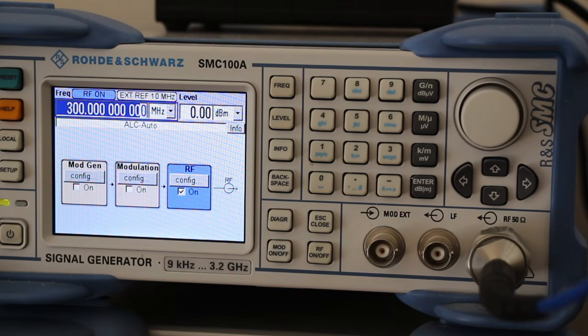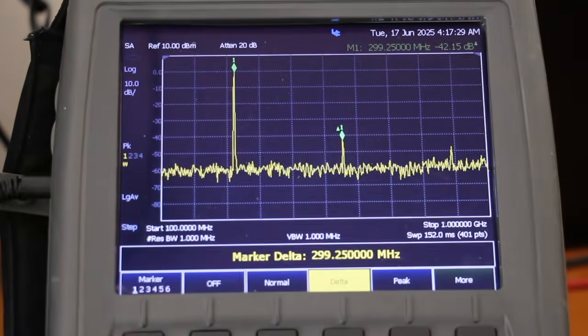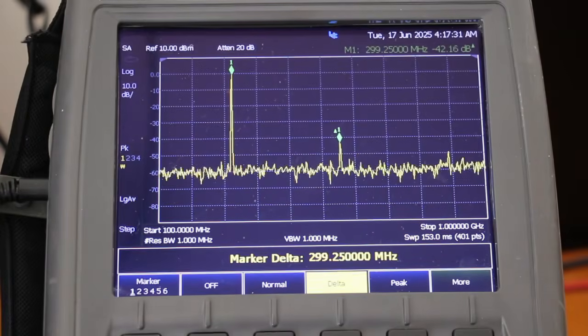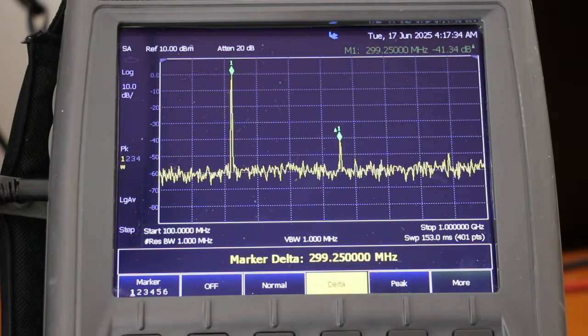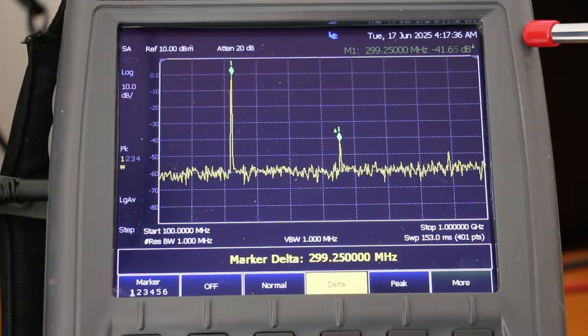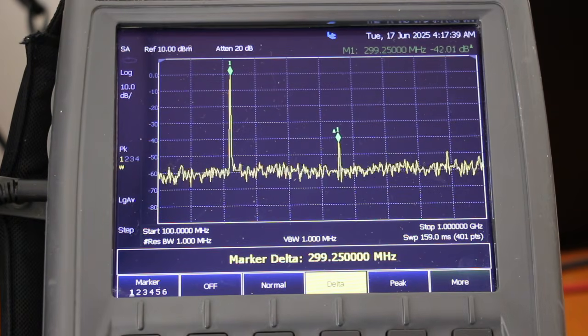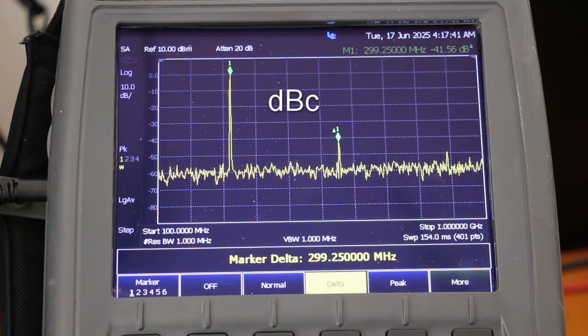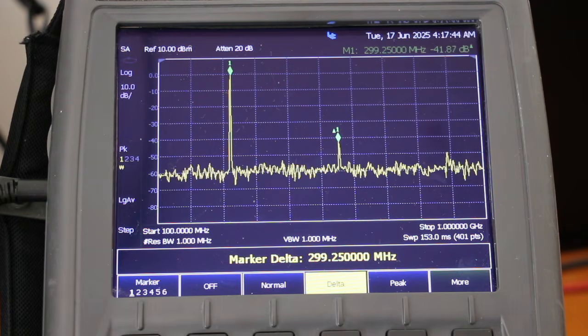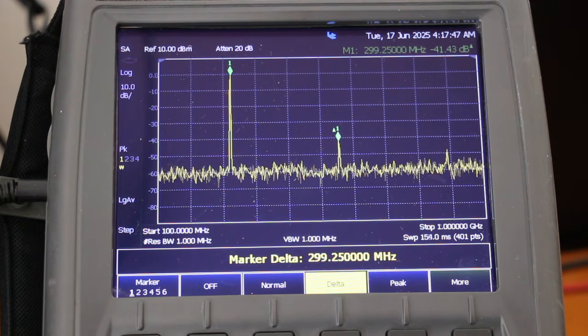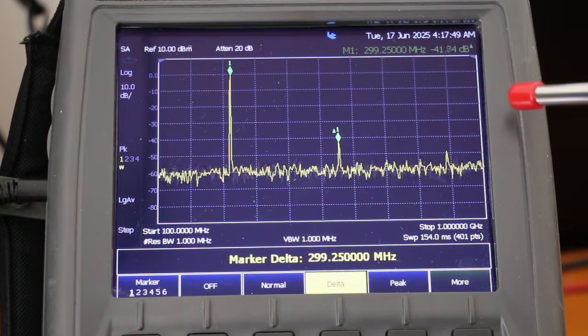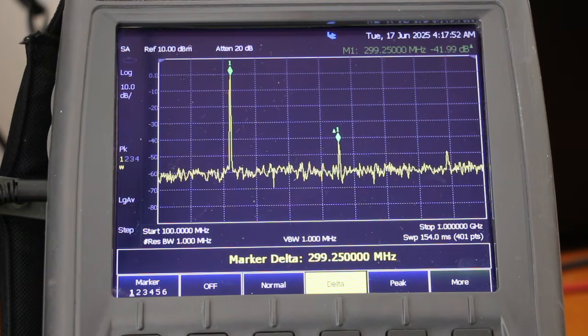Now let's check the purity of the generator with a spectrum analyzer. I set here 300 megahertz, 0 dBm. Let's see what's happening at the spectrum analyzer. This is a delta marker. We have here minus 42 dBc for the second harmonic, and the third harmonic is about 10 dB below the second harmonic.